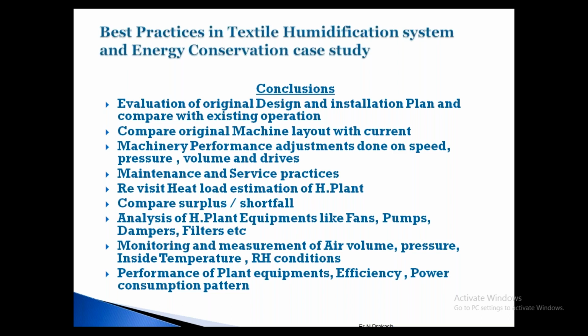Okay. From the energy point of view and total best practice on humidification, the first thing is we have to evaluate the original design, then the installation plan, and compare it with the existing operation. There will be changes of machine, changes of operation, everything. First we have to do that. Then compare the original machine layout. Wherever we go, we have to get the machine layout first.